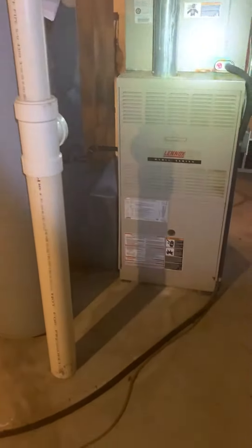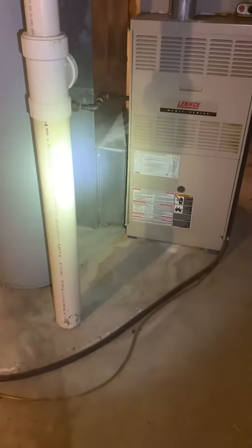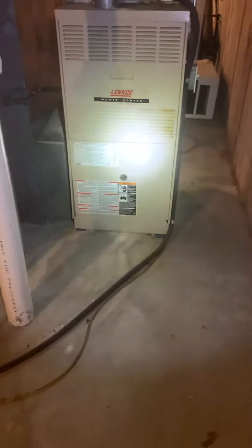Looking at replacement of a full system — we got a Lennox unit, 110,000 BTU. We do have the spacing here for the 5-inch filter and want to utilize that. The return is the correct size already and will stay in place; that's 13 by 26. We want to modify the electric, the gas piping, and flue piping.